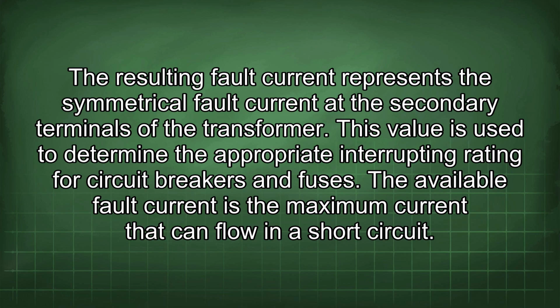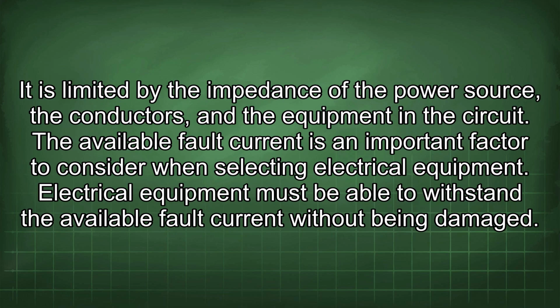The available fault current is the maximum current that can flow in a short circuit. It is limited by the impedance of the power source, the conductors, and the equipment in the circuit. The available fault current is an important factor to consider when selecting electrical equipment. Electrical equipment must be able to withstand the available fault current without being damaged.